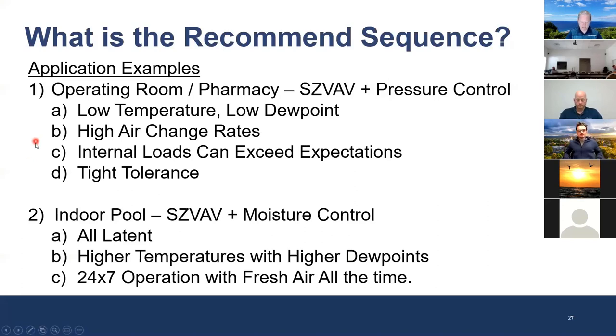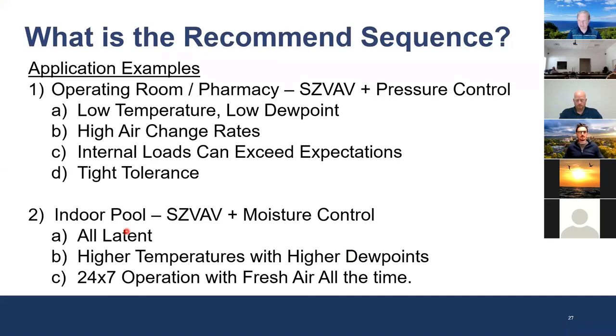Indoor pools are still a single zone VAV with moisture control, using adjustable fans as necessary. If occupied, you still need fresh air, but you don't need as much load. Why use VAVs? To maximize moisture removal and only provide the cooling necessary for the specific room. I'm not a huge fan of VAV when I see them with supply reheat using electric strip — all the savings from the VAV get lost if it doesn't match the load characteristics. The indoor pool application is all latent — higher temperatures with higher dew points, 24/7 operation. The indoor design is 84°F at probably a 66–68°F dew point. Going back to our poll question: you can absolutely economize on a pool based on the dew point question. 66°F and raining outside gives you the capability to dehumidify an indoor pool environment.